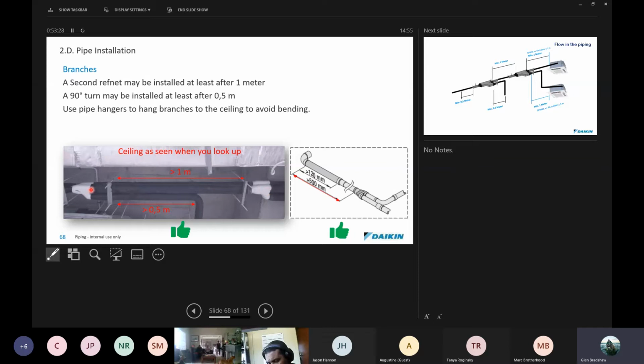These are horizontal. These RefNets must be a minimum of a meter apart. You can have more, but you cannot have less than a meter. So anytime you've got two RefNet joints, don't come out of one straight into another. At all times, any bends on the indoor units must have 500 millimeters of pipe. You can use hangers and RefNet joints.